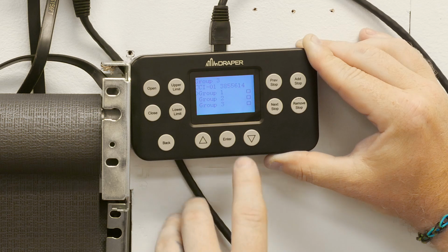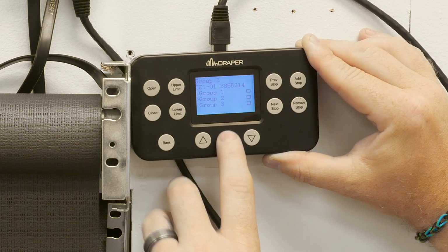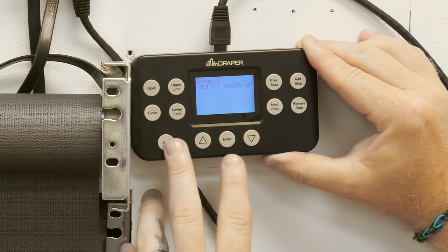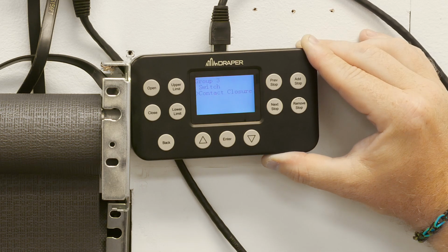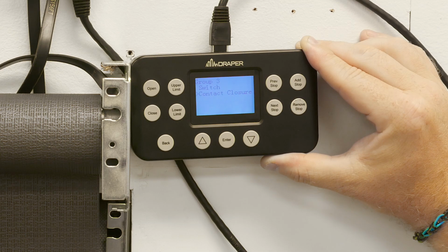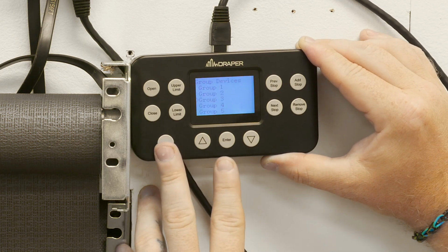For this instance, I only want my second set of dry contacts to be part of group 3, so I'm going to select that and hit enter. That box is now checked. I can hit back, and the second set of dry contact terminals is now programmed to group 3. Meaning my group 1 and group 3 from my contact closure interface are masters, but my second set of dry contacts is only programmed to group 3, so it gives me both individual and master control for flexibility.